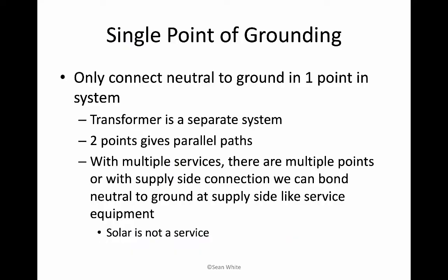Kaboom! Let's talk a little bit about the single point of system grounding. And so for each system, and a transformer would separate a system, but for each system, you're going to have one point in that system where there's that single point of system grounding. If you are in a house right now and you feel like checking it out and you're not afraid of getting electrocuted, yeah, you should be afraid of getting electrocuted. Don't do it is what I say.